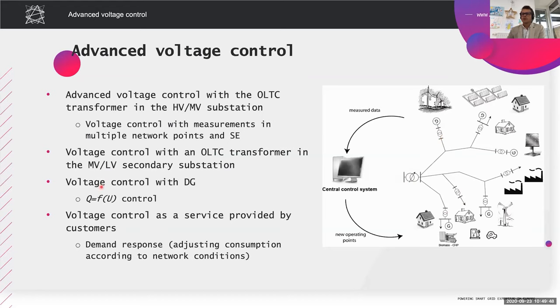The third option, which is often used, is that distributed generators, which are connected to low voltage or medium voltage level, control the voltage by means of reactive power. So a distributed generator measures the voltage at its connection point and controls this voltage by means of reactive power. This is why I'm noting here the reactive power as a function of the voltage at the connection point. This is a requirement in many networks today, so at many distribution network operators. So the distributed generators are required to control the voltage by means of reactive power control.